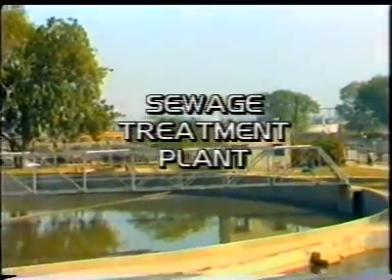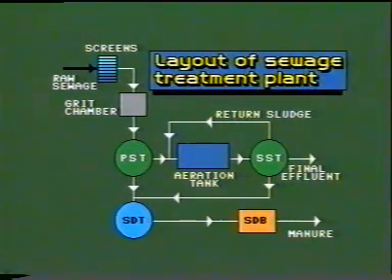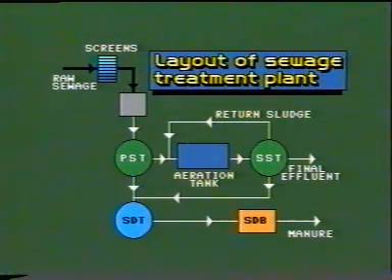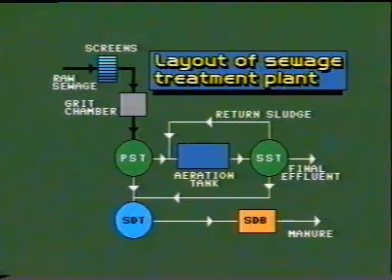Take a look at a sewage treatment plant where domestic sewage is being treated. Let us understand the layout through a line diagram. First, raw sewage passes through the bar screens. Thereafter it enters the grit chamber where inorganic matter is removed. After this, sewage enters the primary settling tank where heavier suspended organic matter settles down. The settled material, known as sludge, goes to the sludge digestion tank.